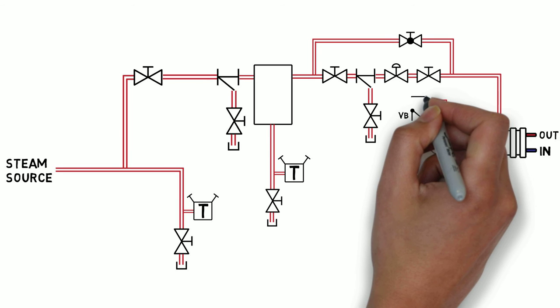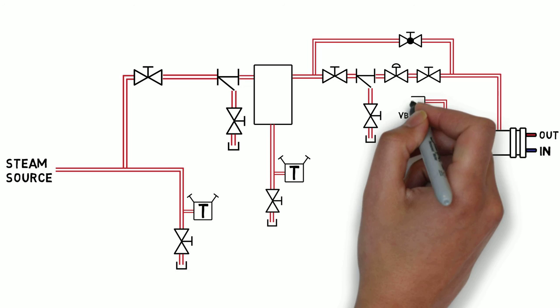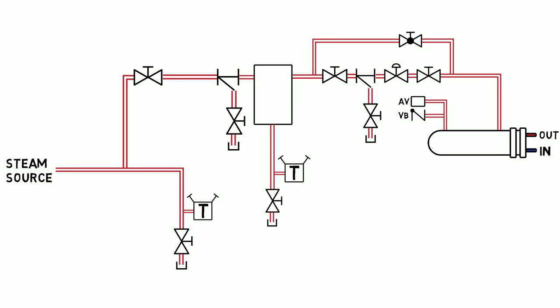Also piped at this location of the shell is a thermostatic air vent, which will discharge air and other non-condensable gases when present. This discharge of this vent should be piped to a safe location.